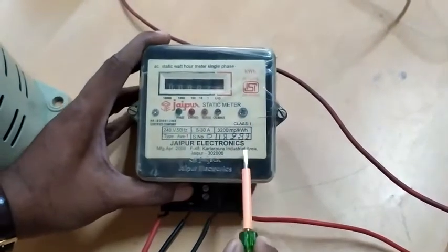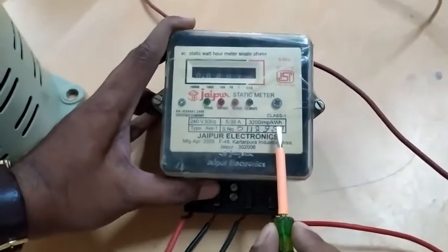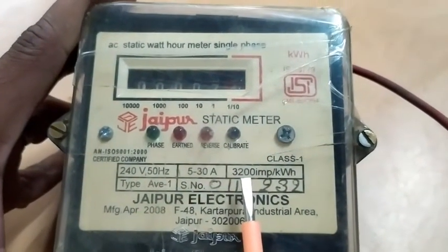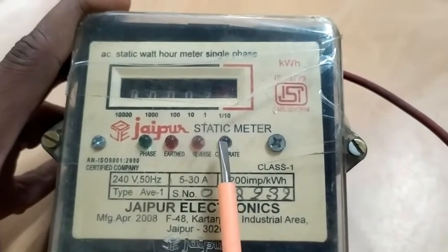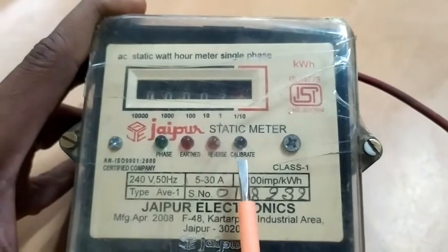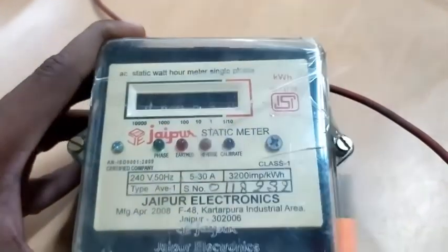In this energy meter, we are having 3000 impulse per kilowatt hour. One unit is having 3000 impulses. Here is the calibrate, it will blink depends upon the one impulse. If we get 3000 total, it becomes one unit.